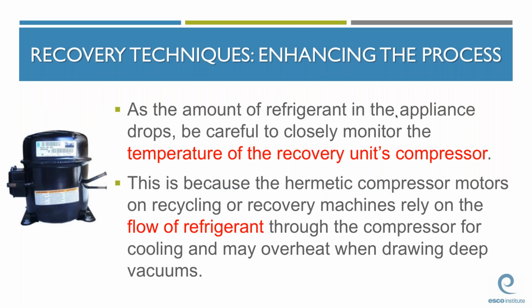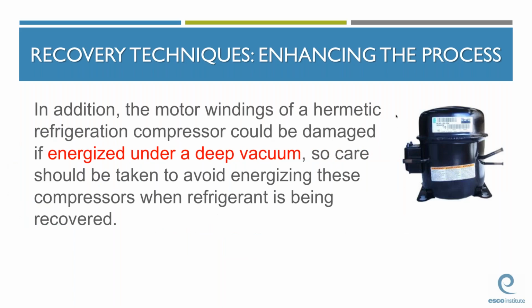During the recovery process, closely monitor the temperature of the recovery unit's compressor. This is because the hermetic compressor motors on recycling and recovery units rely on the flow of refrigerant to cool them. Because of this, the motors may overheat, especially when the system pulls into a deep vacuum. In addition to the hermetic compressor overheating during the recovery process, the windings of a hermetic refrigeration compressor could become damaged if energized while in a deep vacuum. So exercise caution to prevent this from occurring.